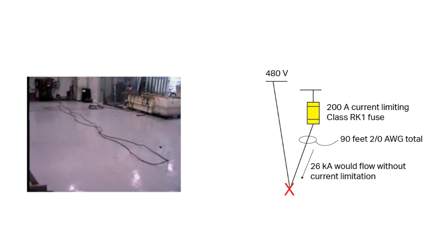In this test, we see a significant reduction in the let-through energy by the 200 amp Bussmann series low peak fuse. The peak let-through was measured at 10,000 amps, clearing in approximately 4 milliseconds. Since the mechanical forces exerted on this electrical equipment are directly proportional to the instantaneous peak current squared, the current limiting fuse reduced the maximum mechanical force let through by over 95% as shown in this equation.